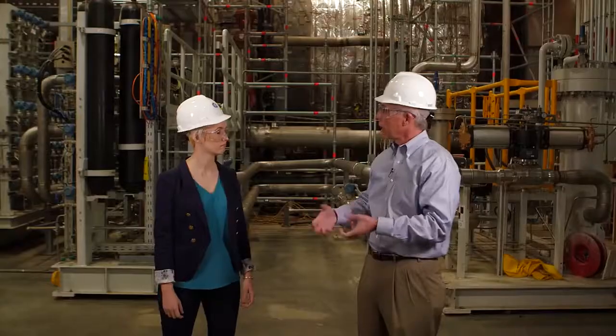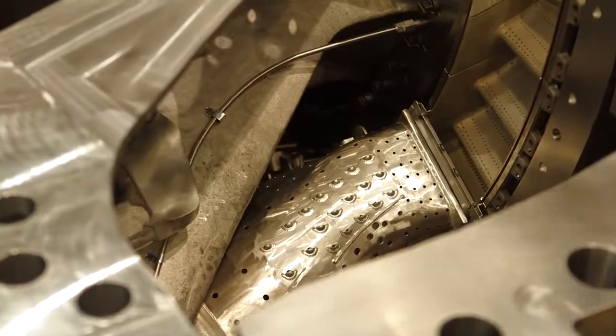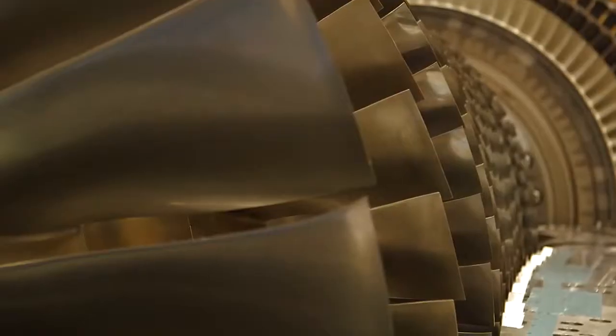The bulk of the air is mixed with fuel and combusted. This is the bang, because this is where the pressurized air combines with the gas or the fuel. And we blow that out through the hot section, or the turbine section. The expansion that takes place when you release that energy creates the torque that turns the generator that produces the electricity.